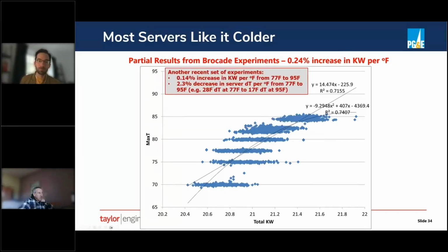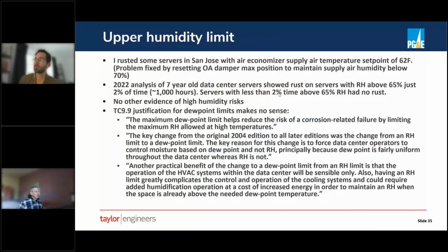Other recent experiments we've run showed a smaller increase in power, and a 2.3 decrease in server delta T. Right. And so one of the other things that happens when the server fans speed up is that they need more air, right? So the delta T between what's going into the computer and coming out of it goes down as you provide warmer air to those computers. So not only using more power, but you need to feed it with more air. So there is a trade-off there as well. Again, it's a trade-off worth making, at least on an energy efficiency basis.